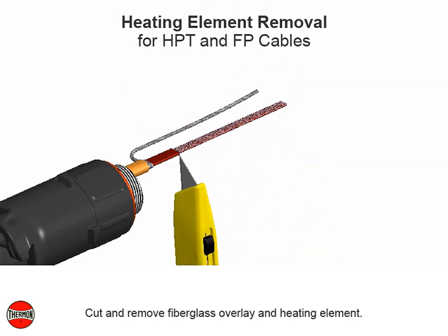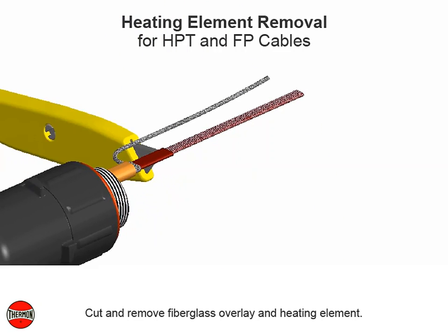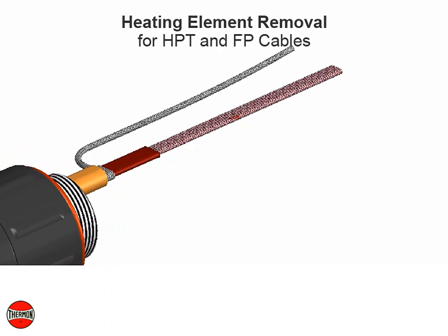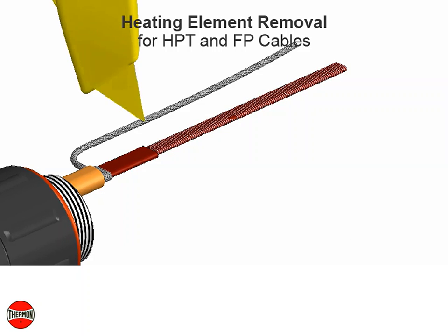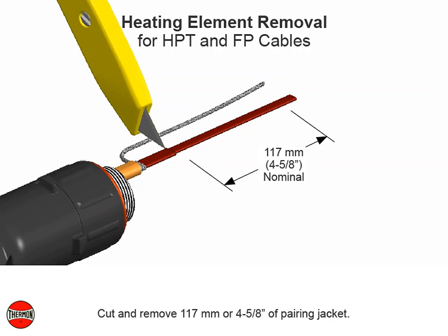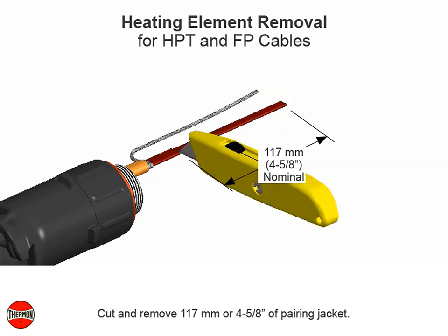Cut and remove fiberglass overlay and heating element. Push any remaining heating element wire under the primary insulation jacket. Cut and remove 117 millimeters or 4 and 5 eighths inches of pairing jacket.